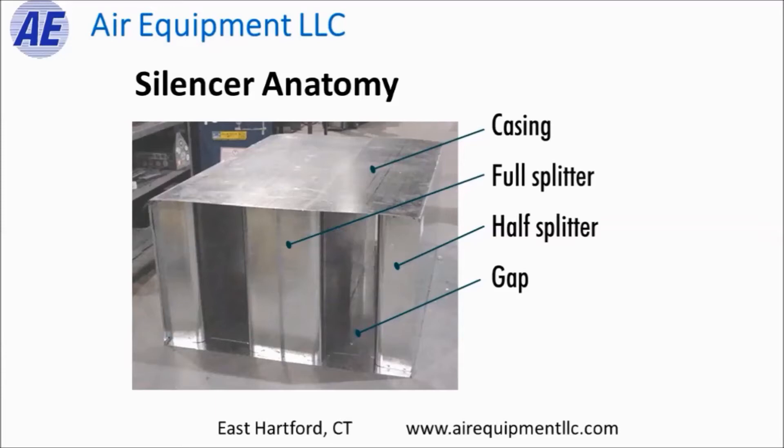The sound trap is constructed out of the same material as the adjacent ductwork, usually galvanized steel, and the casing is most often the same dimension as the ductwork it's connected to. But inside it's much different than just a piece of ductwork. There are what we call splitters — modules shaped from perforated metal that have a sound absorbing media inside, usually fiberglass — and there are gaps which allow the air to flow through.